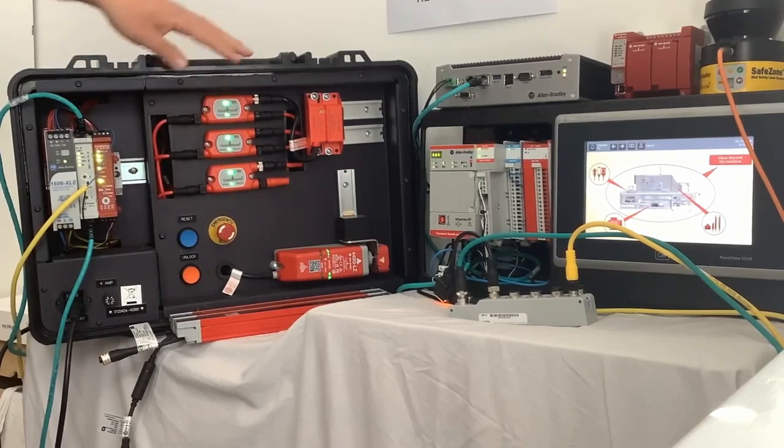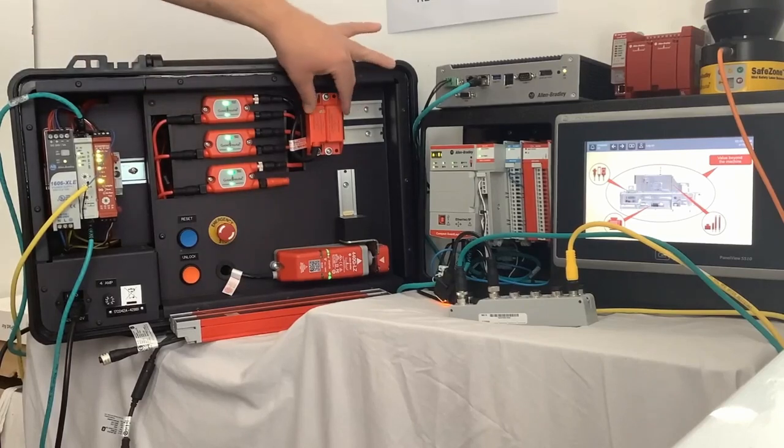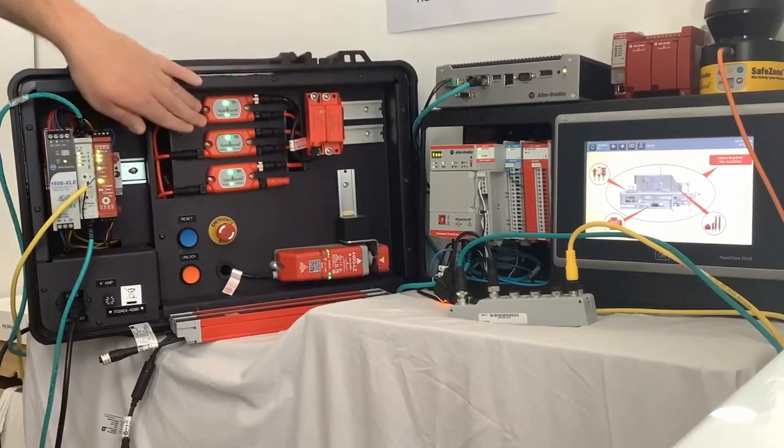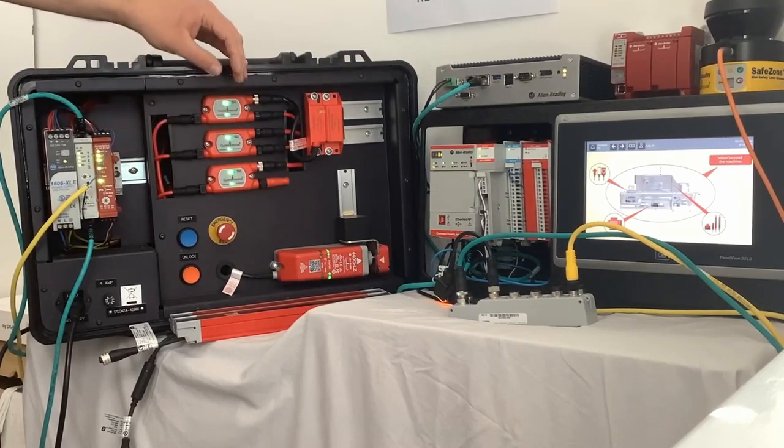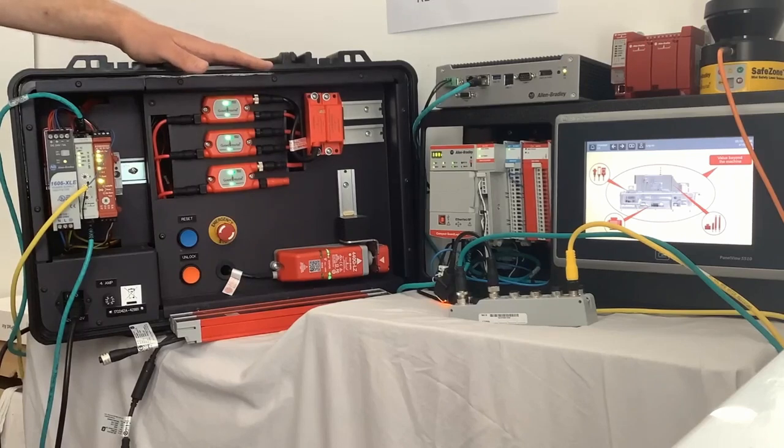So with this technology, you have no risk of fault masking. The way it works is the output from the safety device here, we've got a sensor guard, wires into the smart tap, and the smart tap is doing the diagnostic coverage at that point. So you cannot fault mask. This is really good for retrofitting to existing machines that have dry contacts that we're bringing up to the latest standard.